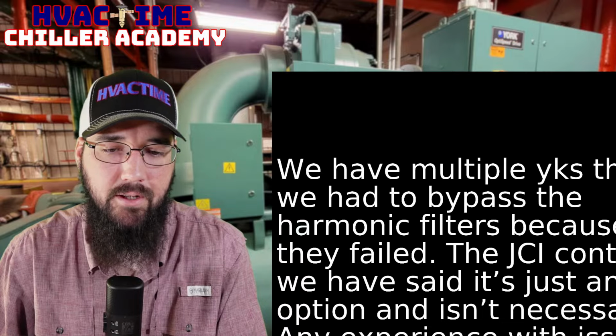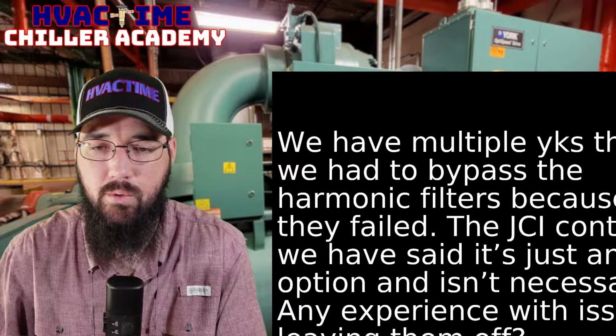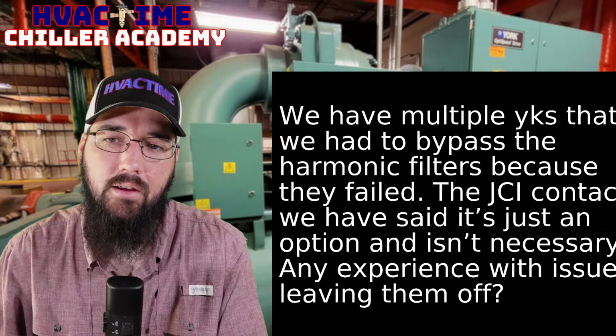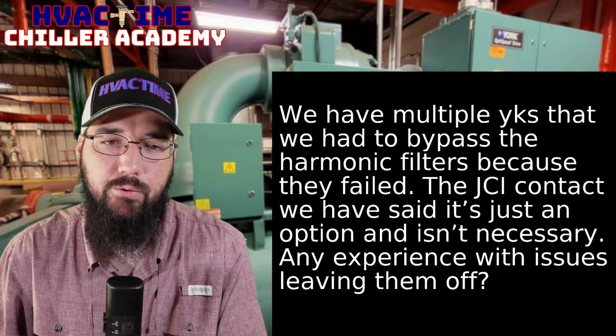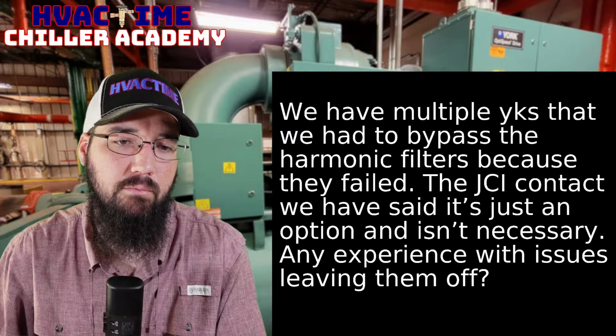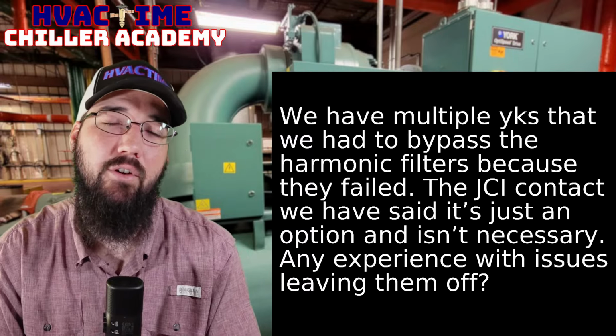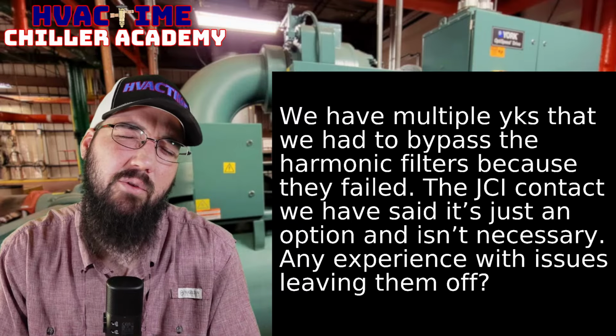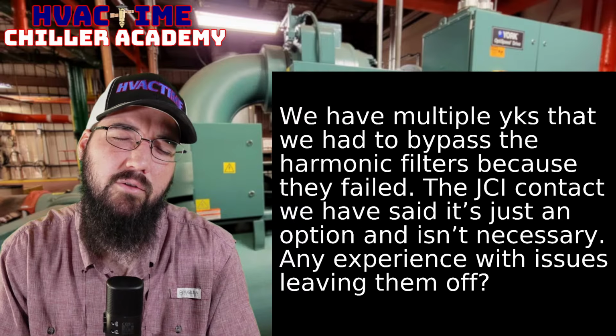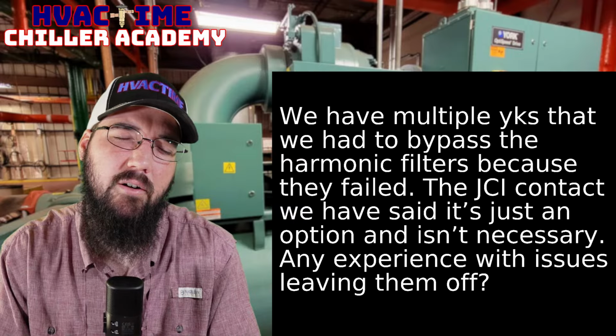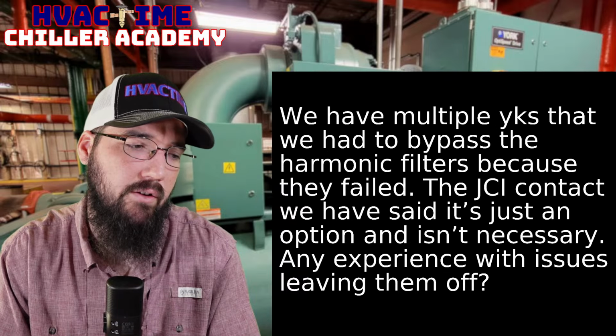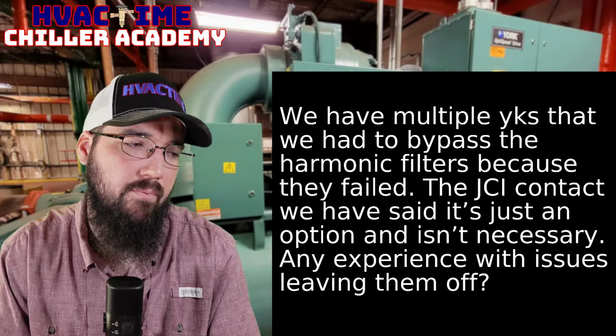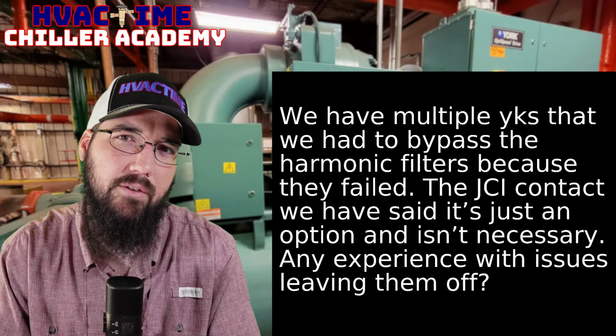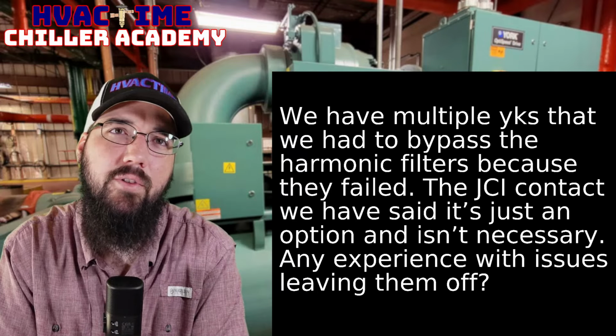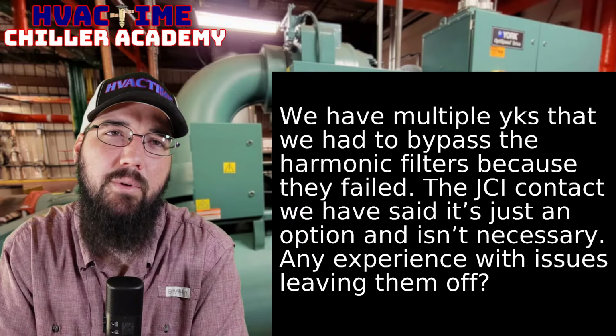So one clarifying question I have is, I'm assuming we're discussing, you said YK. All right, so we got that. So YK is probably a smaller YK, I would assume. So when I say smaller, your motor horsepower is going to be what, the 500, was it 503? The 503 or smaller horse. I guess that would be true even for the 700 up to the 1000 horse. Because once you get above, was it 900 or 1000 horse drives, you start getting into the floor mount panels.